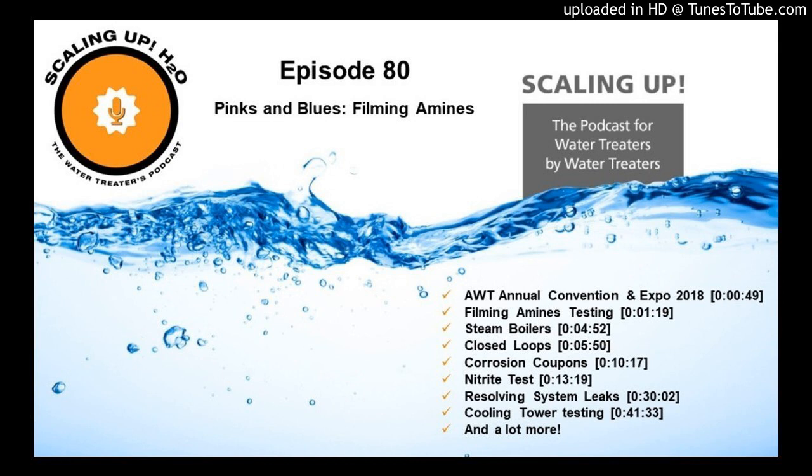Now, we've been using that on an extremely hot system that we would have no hope of putting any of our regular phosphate-based programs in because we would be getting scale. Well, with this, we have been getting great results, and it's a molding facility. And when they take those molds apart, they are really clean. They look really good.